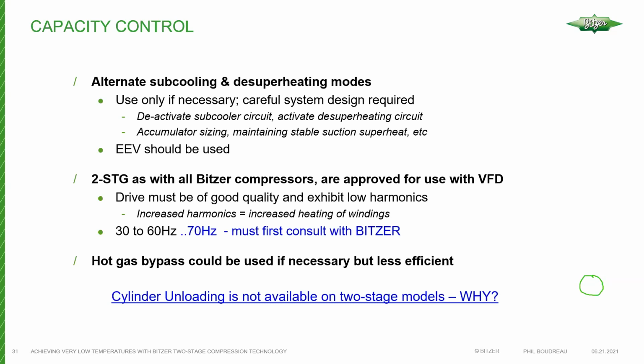Two-stage compressors, as with all compressors, are approved for use with a variable speed drive or variable frequency drive. We just have to be aware of the speed range. Generally speaking, it's 30 to 60 hertz for the two-stage series. In some cases, we can actually operate that compressor up to 70 hertz. But again, in this case, you would want to consult with one of us at BITZER so we can take a look at the application and see if this is achievable and safe for the compressor.